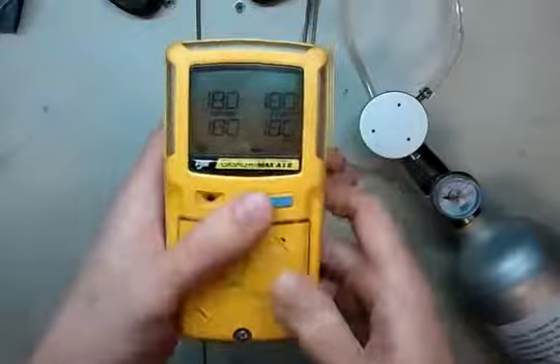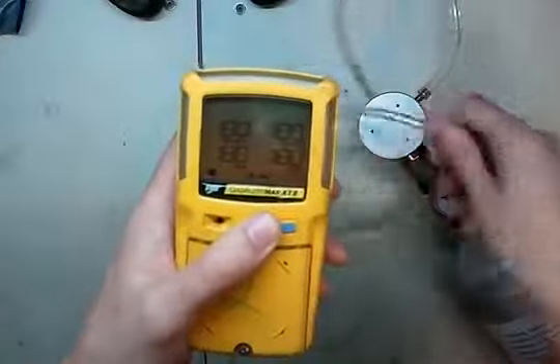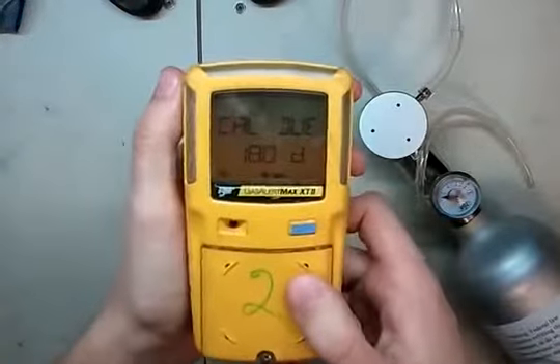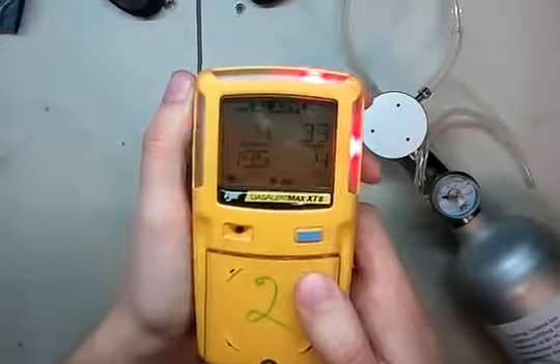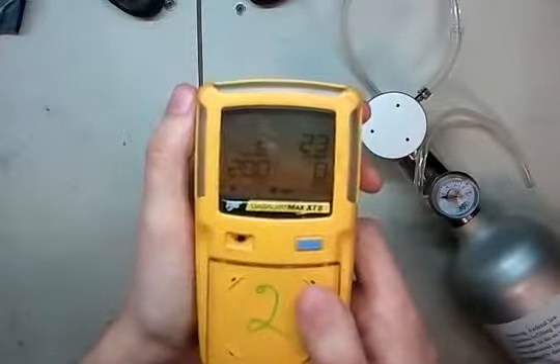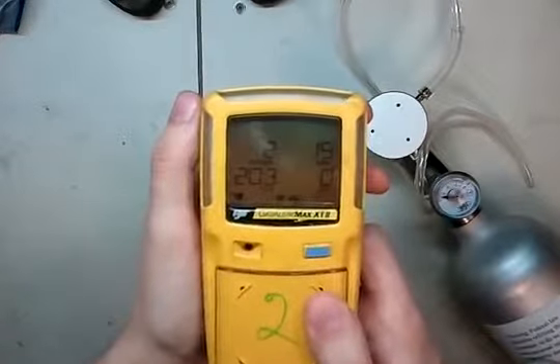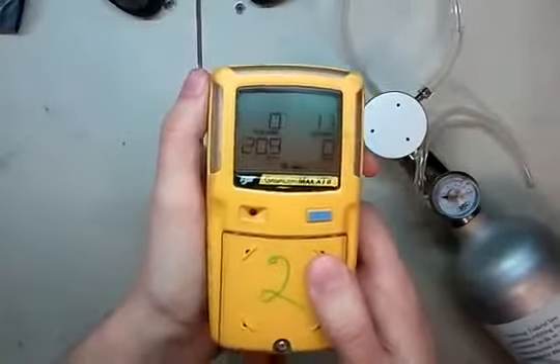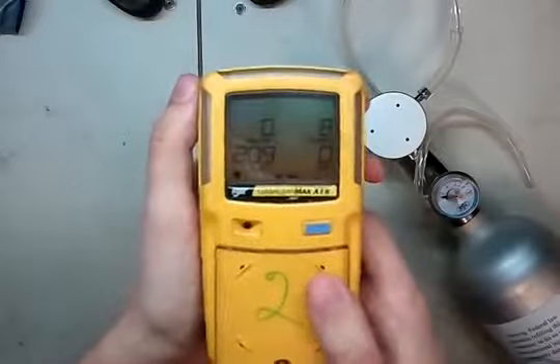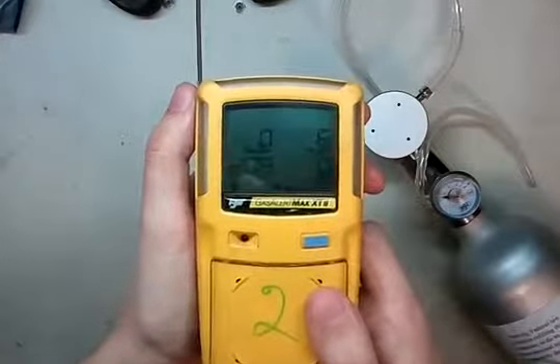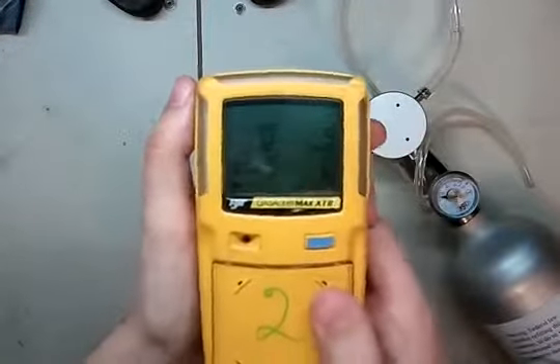Okay, now we're good. Cal done. So go ahead and just pop that hose out there. It's going to come up with a cal due. Now it says 180 days to calibration due. Don't wait 180 days to calibrate. Calibrate every 30 days, bump daily, and that way you keep yourself safe. You've probably heard me rail about this before, but 180 days is way too late to calibrate. But that's all you need to know.